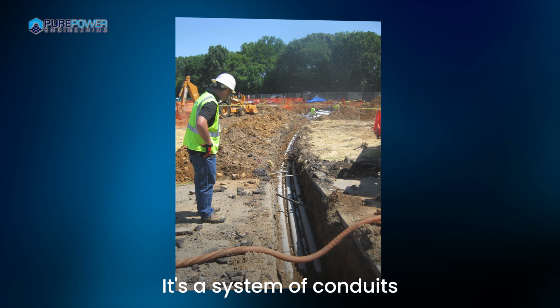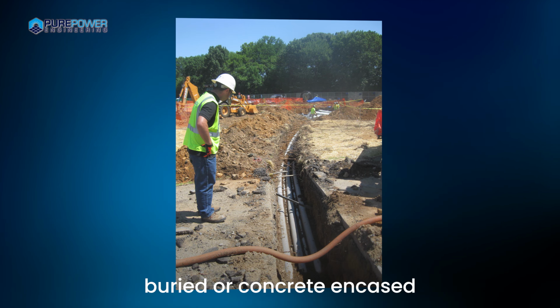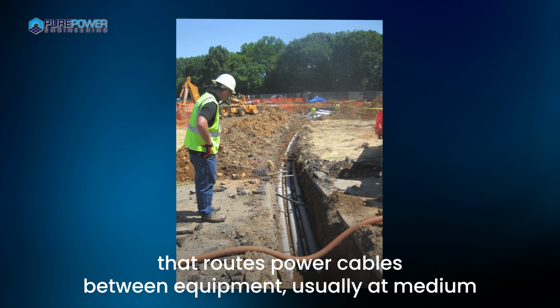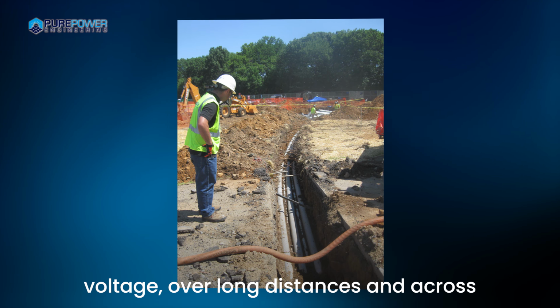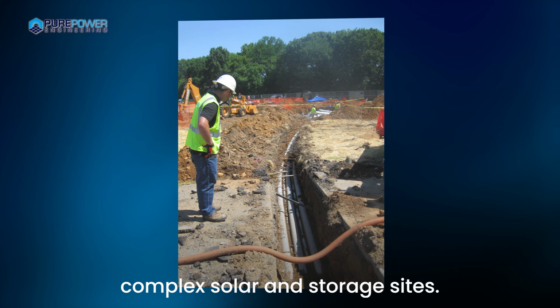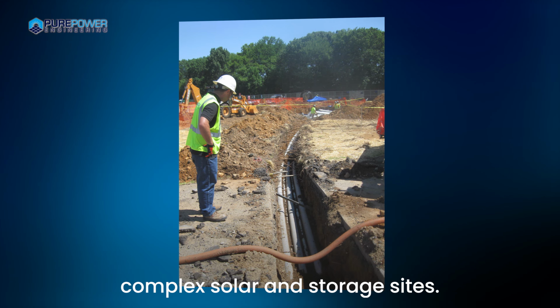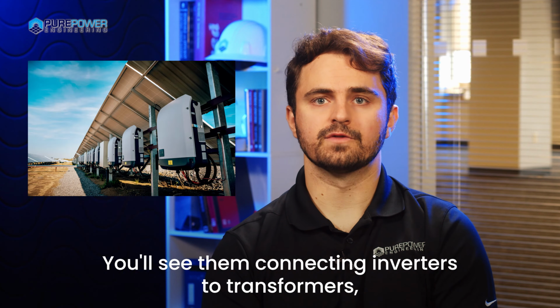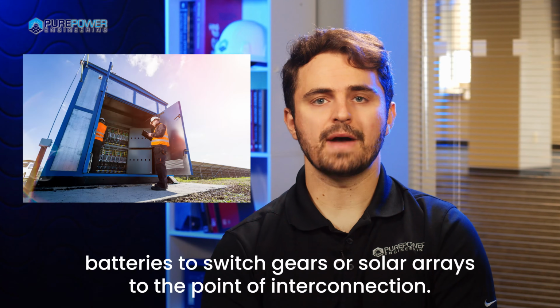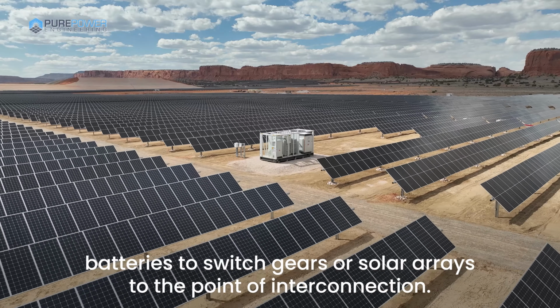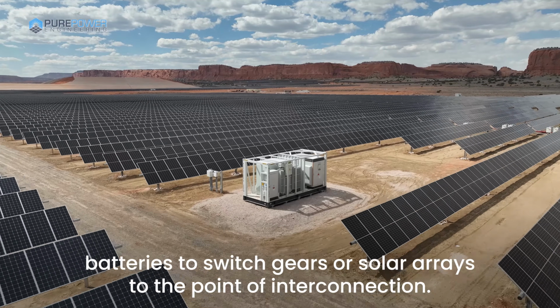It's a system of conduits, buried or concrete encased, that routes power cables between equipment, usually at medium voltage, over long distances, and across complex solar and storage sites. You'll see them connecting inverters to transformers, batteries to switchgears, or solar arrays to the point of interconnection.